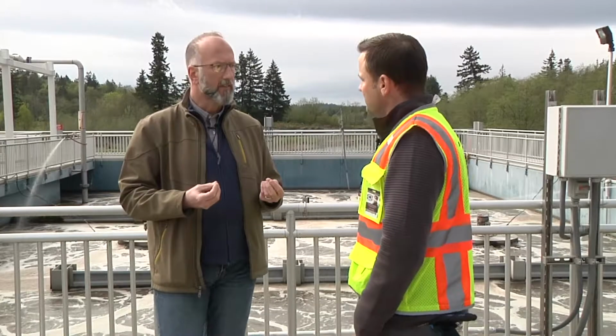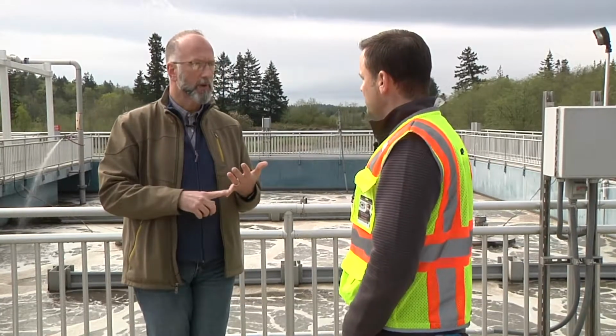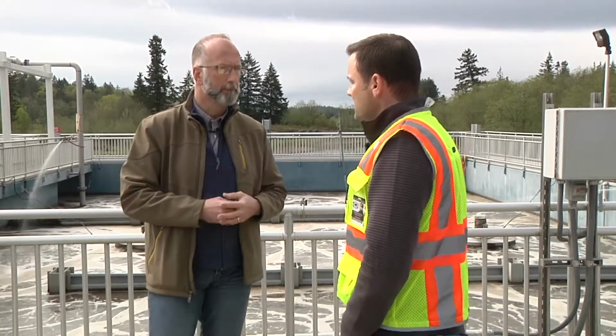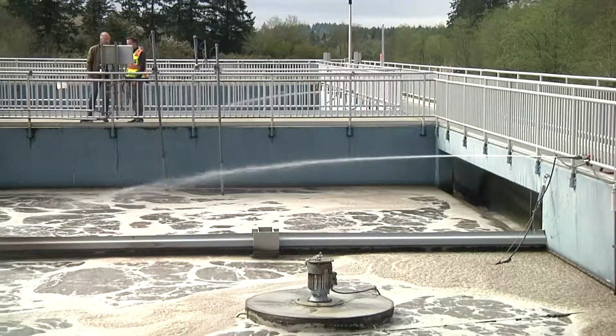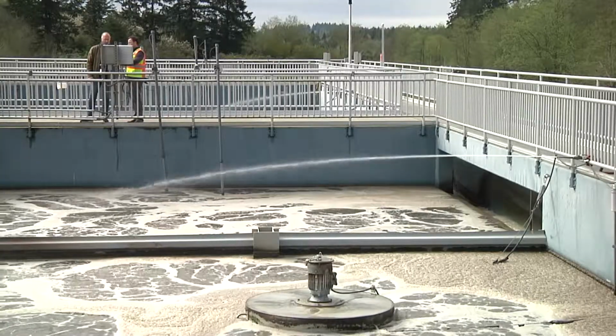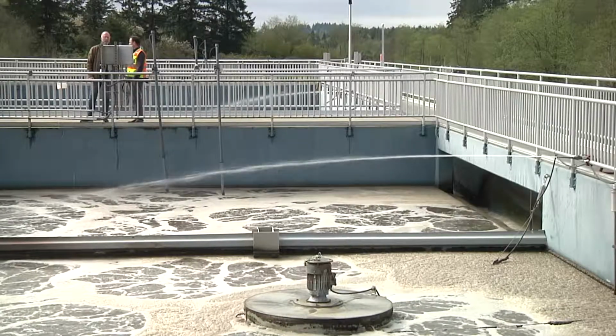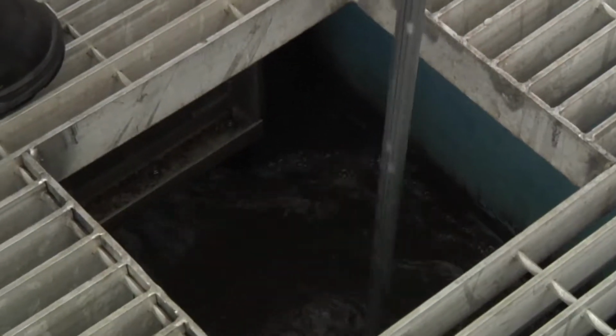So how do you keep track of those to make sure they're getting what they need and monitoring them? We have multiple ways. We have inline probes that give feedback immediately to operators for levels of dissolved oxygen, also ammonia and nitrate nitrogen. And then we do laboratory work, the solids analysis - when I say solids I mean the actual organisms themselves. We measure quantity every day and let the operator know how many organisms are in what part of the process.